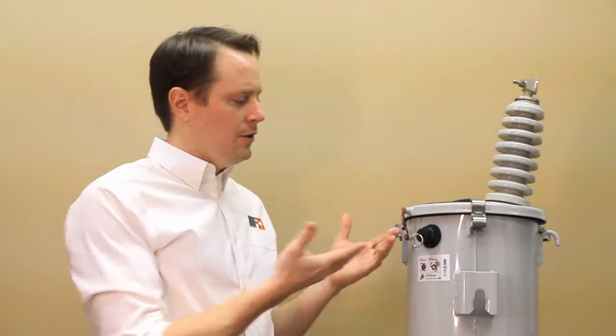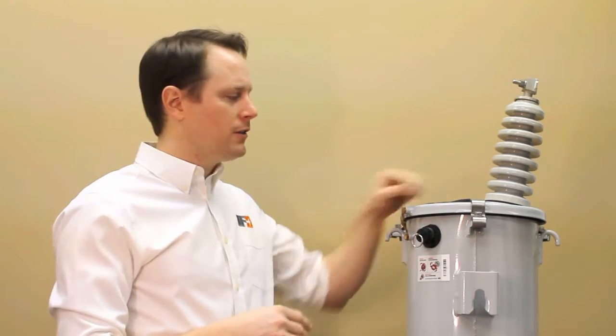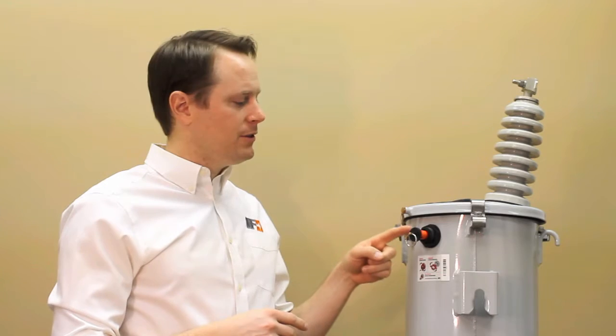Alright, let's talk about tip number 2. We obviously have a transformer, it's out in service, it's ready to go, looking for an internal fault, and all of a sudden, ba-boom, we get an activation. You show up to site, power's out, looking around, and you see the signal, replace the transformer. That's tip number 2. Anytime you have an orange indicator on the side of a transformer, get that out of service, send it back to your shop, put a new transformer in.